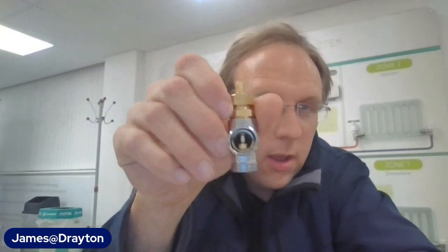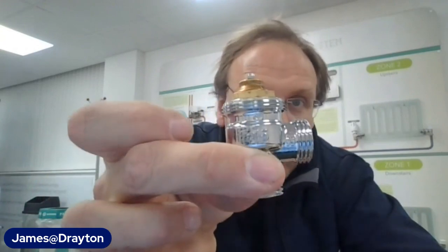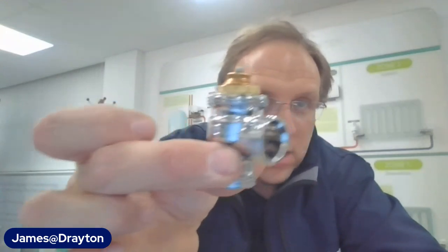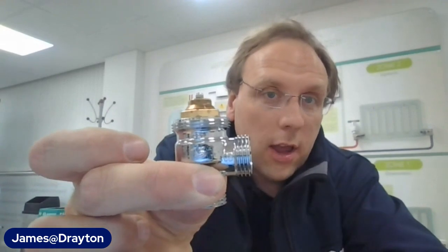So to make balancing as easy a job as possible, you can go around with your lock shield and start throttling these down and doing your differential temperature measurement across the flow and return, where you're adding resistance to a radiator and using the temperature difference to equate to different flow into the radiator. But it's much easier if you use these, because remember, if you set this at 30 liters per hour for, say, this 700 watt radiator, it will be 30 liters per hour flowing into that radiator, regardless of pressure changes on the system, which can arise from other valves shutting down, or just the temperature going up in the system.